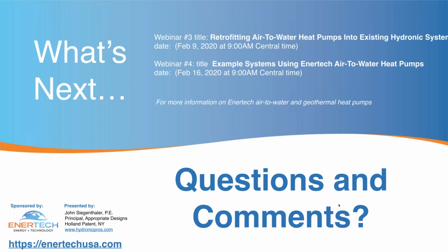We do. So the first question is, what is the lowest outdoor temperature that it will produce hot water? Well, the Enertech heat pump's actually rated down to minus 13 degrees Fahrenheit. So we're still getting water at a usable temperature with a low temperature hydronic distribution system. But I want to stress, at those conditions, our capacity and our COP are low. But if the person's just asking, is there a temperature at which this thing can't work anymore, it's actually rated to operate right down to minus 13.